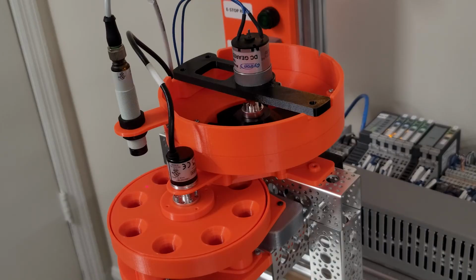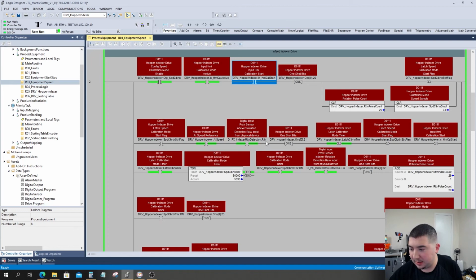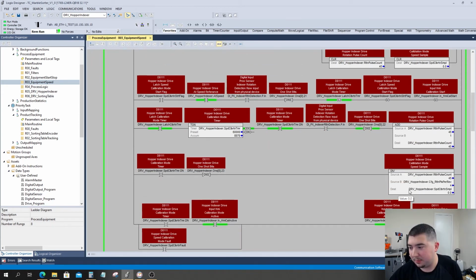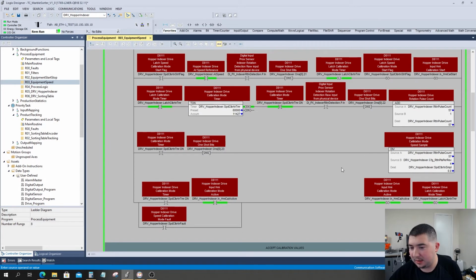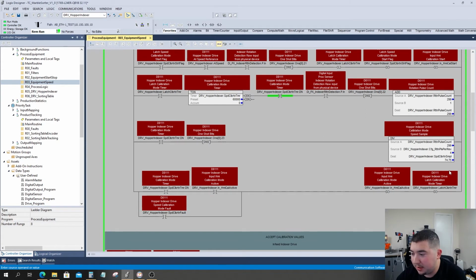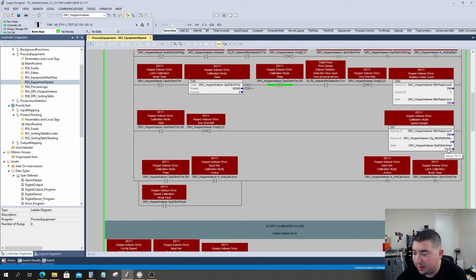And now we'll do a start on the speed. As you can see, the motor is now running, and we're counting our actual pulses per revolution. It's going to take a minute, so let's run the cycle, and after it's done, we'll check the result. Alright, so our speed test has completed. We got 299 pulses for a total of 74.75 revolutions per minute.